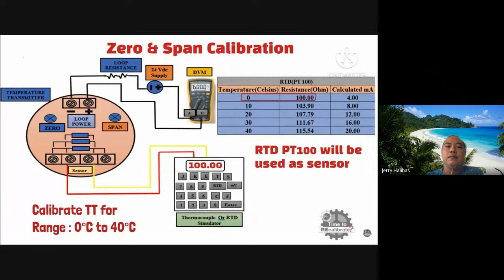Now, let's start with zero calibration. As you can see from the resistance table that RTD-PT100 has a resistance of 100 ohms at 0 degrees Celsius. Now, set 100 ohm resistance in simulator, and apply this resistance value to transmitter. And measure milliampere in DVM. Measured milliampere should be 4 milliamperes. If it is not 4 milliamperes, then adjust to 4 milliamperes by rotating zero adjustment screw.